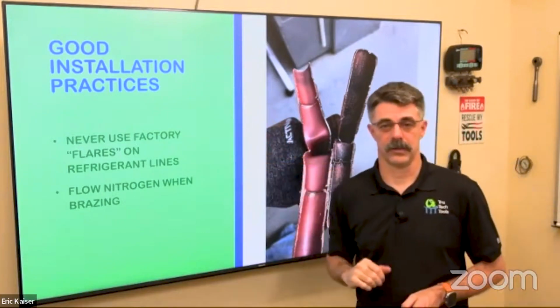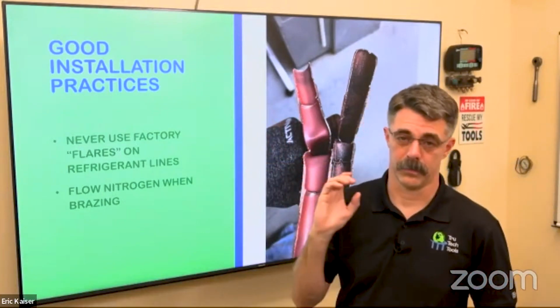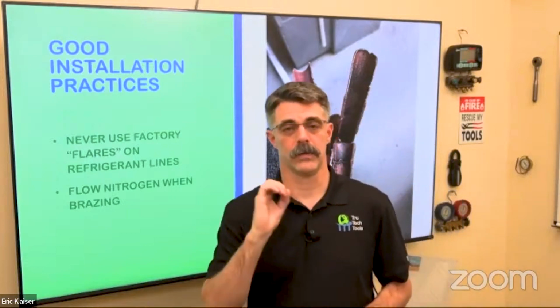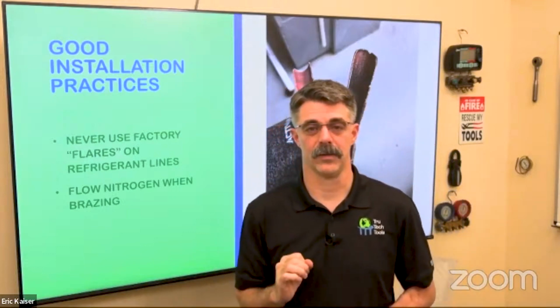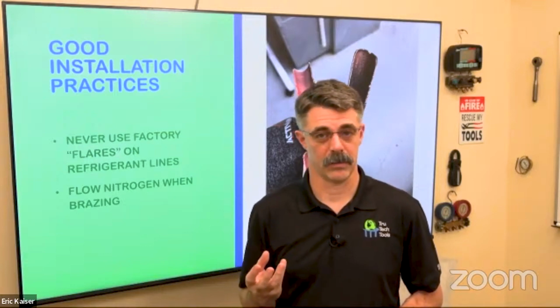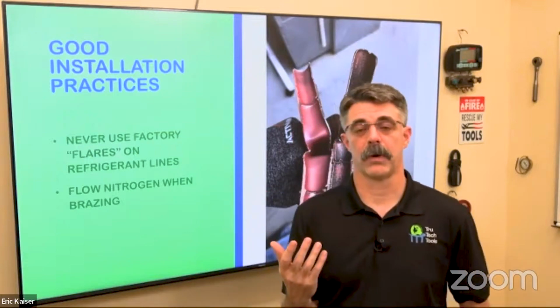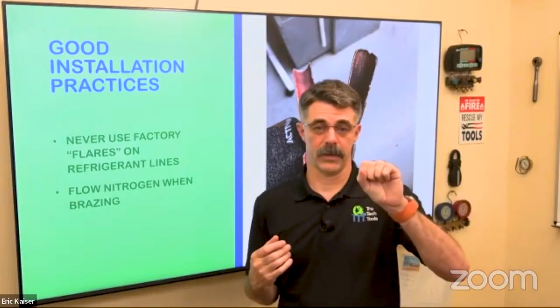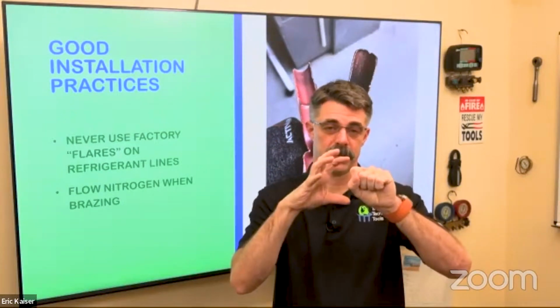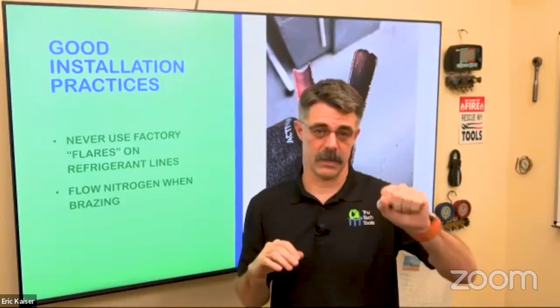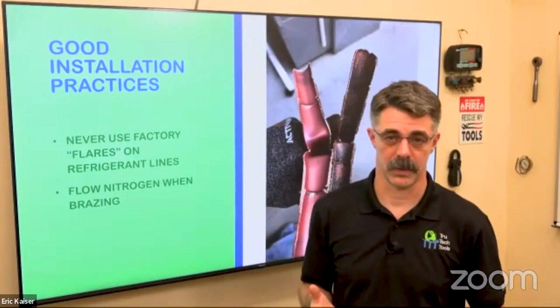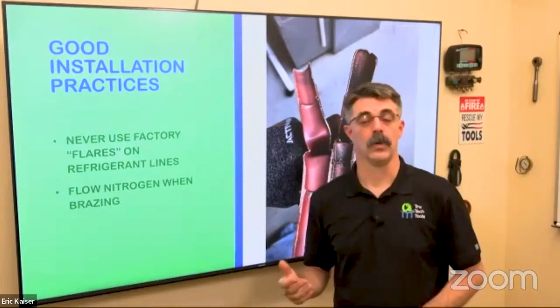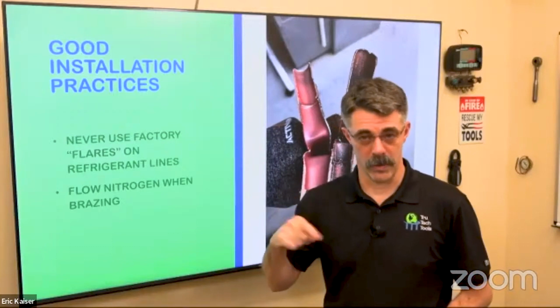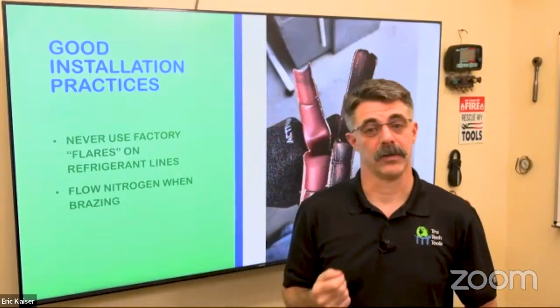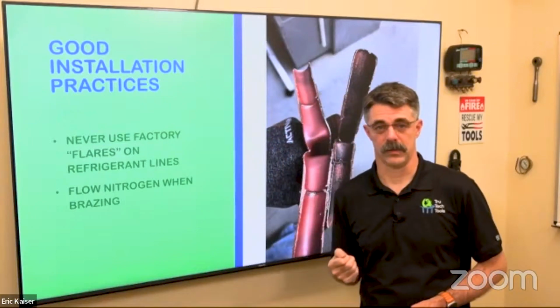On refrigerant line sets, especially on mini splits or ductless units where we're flaring line sets, do not use the factory flares on those lines because they're not actually a flare. When the factory ships those copper lines out to us, they put a nut on the end of the line and they press down and push that copper out just enough to hold the nut on and keep the flare nut that they ship with the line from falling off. That's not a good flare. We need to cut that off, reflare the end of that line with a good smooth flare, and then put it together. Otherwise, we're going to end up with leaks.